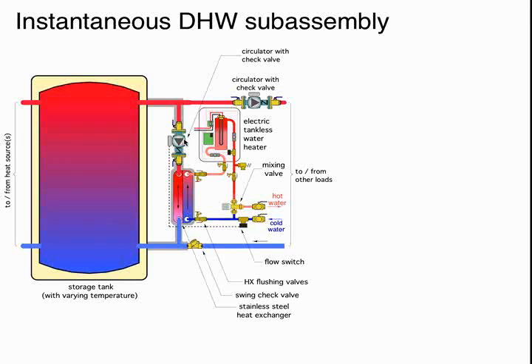All right, instantaneous domestic water. We looked at this assembly earlier. Brazed plate, stainless steel heat exchanger. This could be a standard hydronic circulator, cast iron circulator with a check in it. I'm showing a thermostatically controlled electric tankless water heater as our auxiliary heating device. And the basic idea is this.